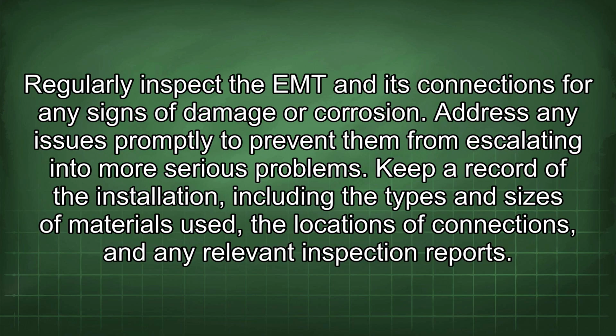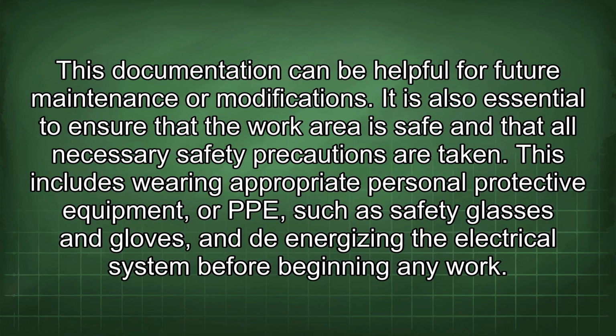Regularly inspect the EMT and its connections for any signs of damage or corrosion. Address any issues promptly to prevent them from escalating into more serious problems. Keep a record of the installation, including the types and sizes of materials used, the locations of connections, and any relevant inspection reports. This documentation can be helpful for future maintenance or modifications.